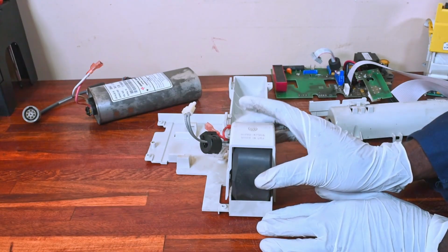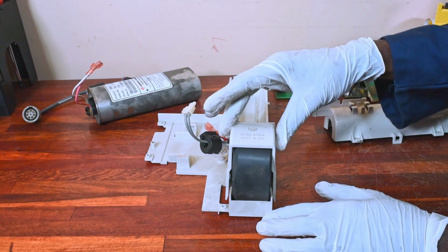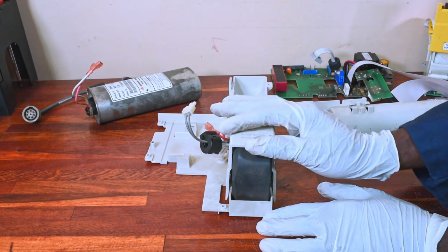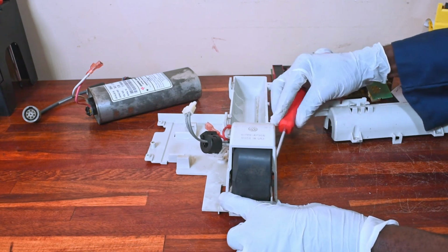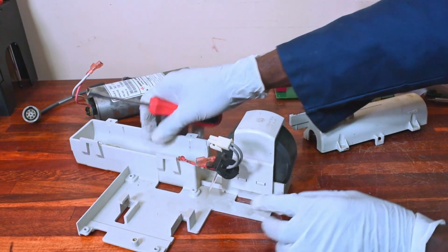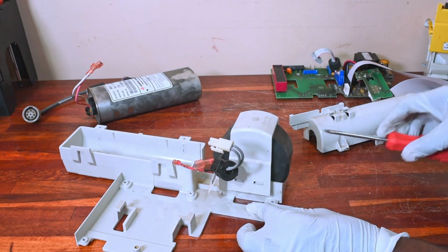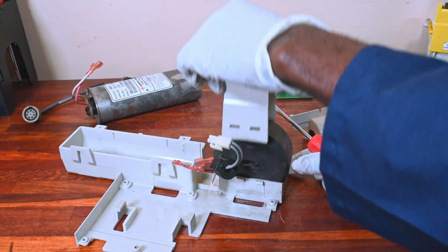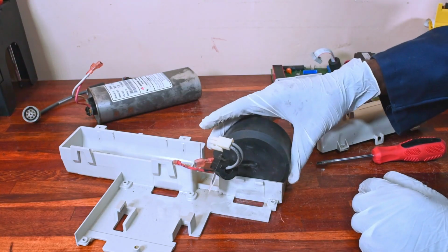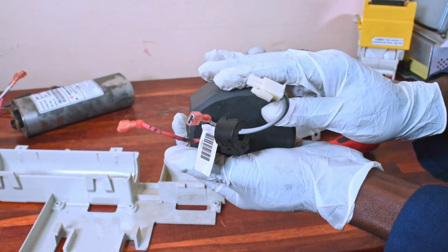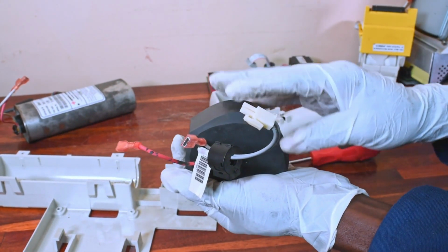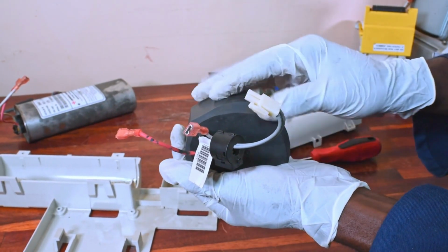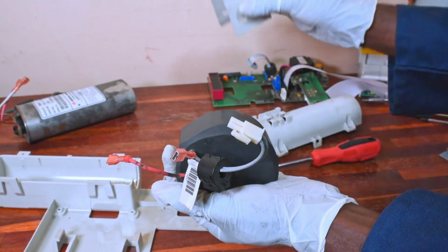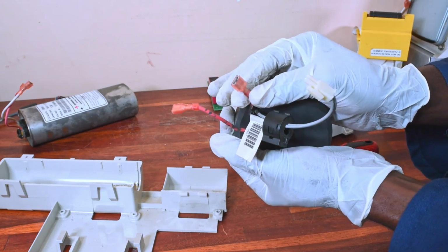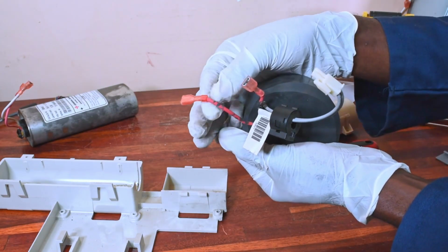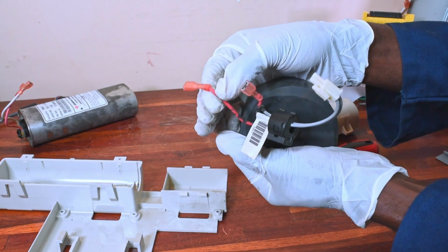Remaining on the assembly is the patient inductor. The inductor can be removed by removing the retaining clip that secures the inductor using a flathead screwdriver. Right here is the patient inductor. During replacement, the inductor wires should face towards the center of the chassis, followed by installation of the plastic retaining clip. The shortest lead wire from the inductor should be connected to the shortest lead wire on the patient relay, with this longer wire from the inductor connected on the high voltage control board.